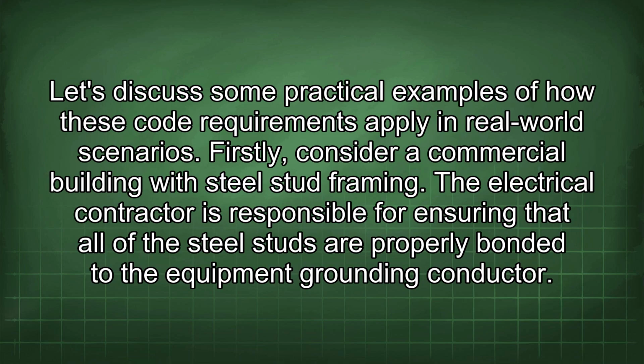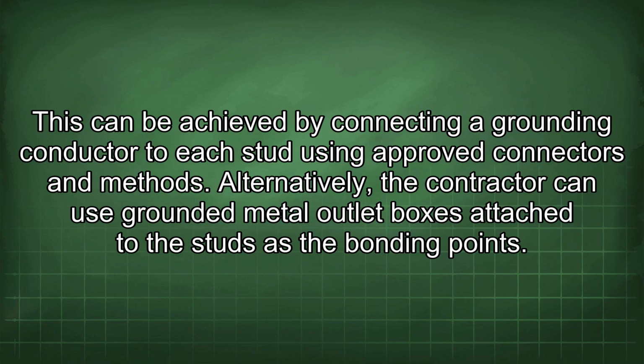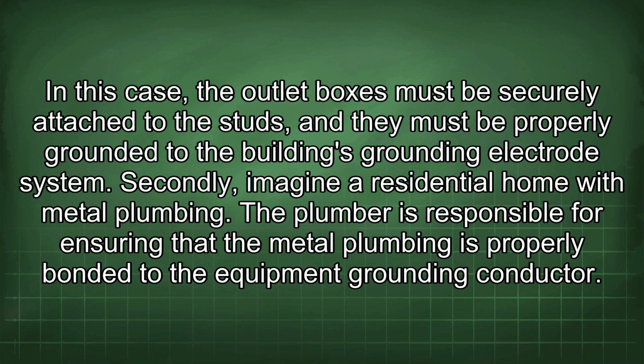Let's discuss some practical examples of how these code requirements apply in real-world scenarios. Firstly, consider a commercial building with steel stud framing. The electrical contractor is responsible for ensuring that all of the steel studs are properly bonded to the equipment grounding conductor. This can be achieved by connecting a grounding conductor to each stud using approved connectors and methods. Alternatively, the contractor can use grounded metal outlet boxes attached to the studs as the bonding points. In this case, the outlet boxes must be securely attached to the studs, and they must be properly grounded to the building's grounding electrode system.